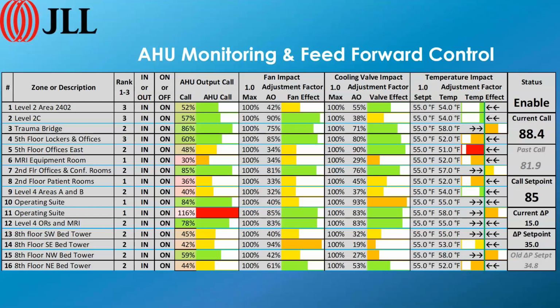That's a good question. We don't actually measure or control off of flow, and there are some reasons for that. The current methods being used for measuring flow are unreliable. I have yet to see a flow meter that is going to stay in calibration for longer than a year, and most of them don't last longer than 4 months. So using them as a control point is very problematic. They're interesting pieces of information, and I might rely on them a little bit for fault detection.